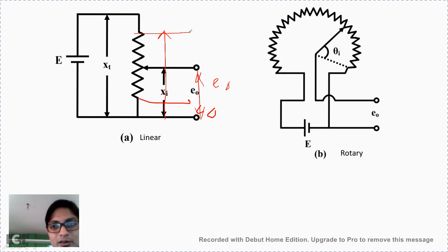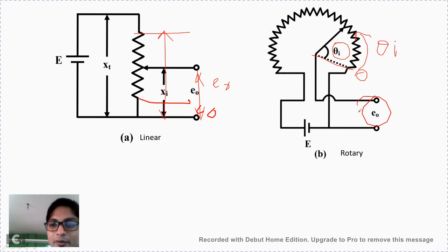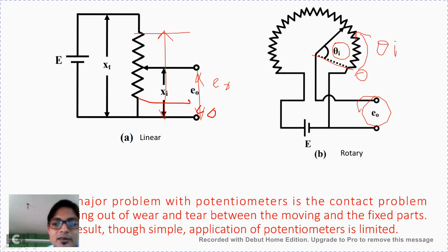Rotary displacement can also be measured with a rotary type potentiometer, which measures angular displacement. Here the input displacement Xᵢ is not linear but angular — it is theta (θᵢ). As angular displacement increases from zero, θᵢ increases and correspondingly E₀ increases, directly measuring angular displacement. However, the major problem with potentiometers is the contact problem resulting from wear and tear between moving and fixed parts, limiting their simple application.